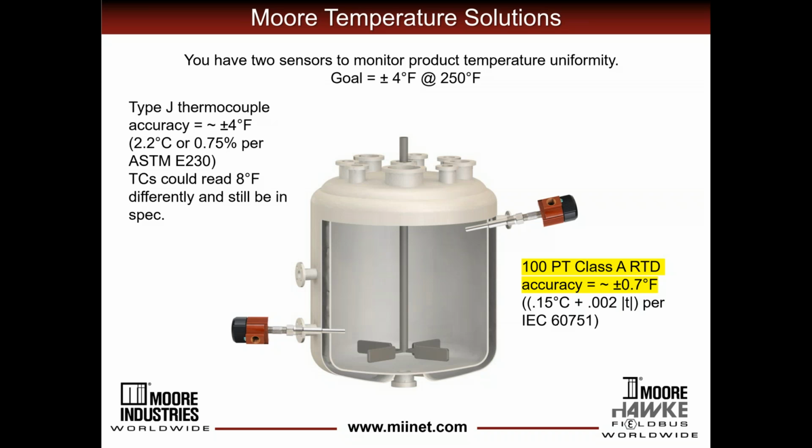If you were to select a 100 ohm platinum Class A RTD, your possible error would only be plus or minus 0.7 degrees F. Two RTDs could differ only plus or minus 1.4 degrees. The solution is better than the two J thermocouples, obviously. Selecting the best sensor for the application greatly affects the accuracy of the measurement, and it helps to meet the demand of the application's goal set by operations.